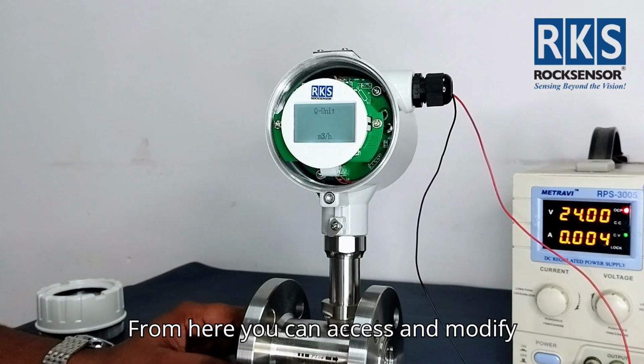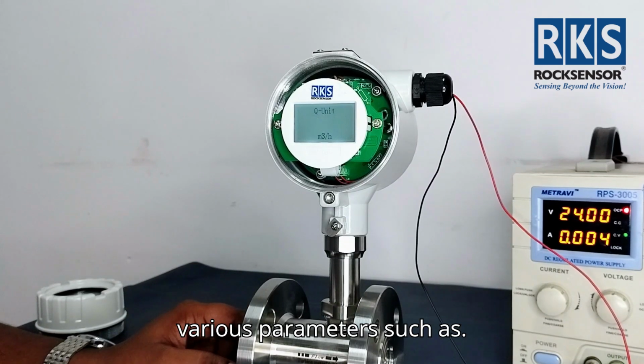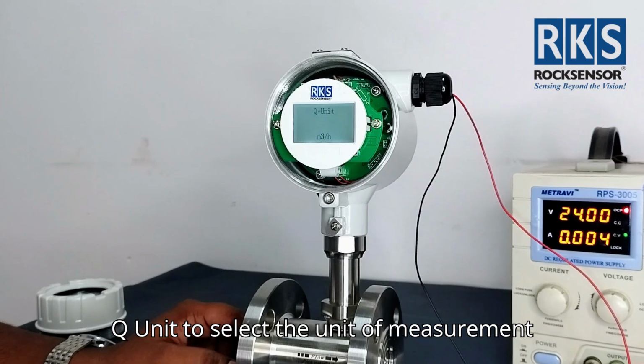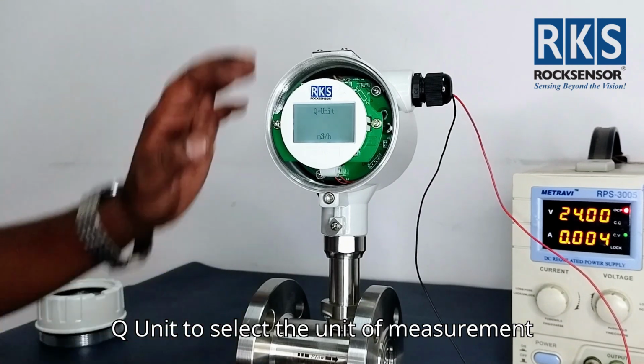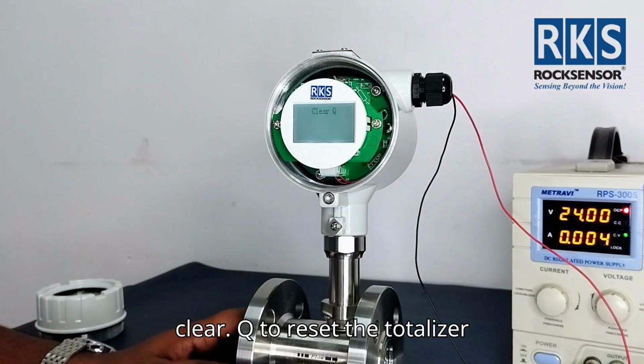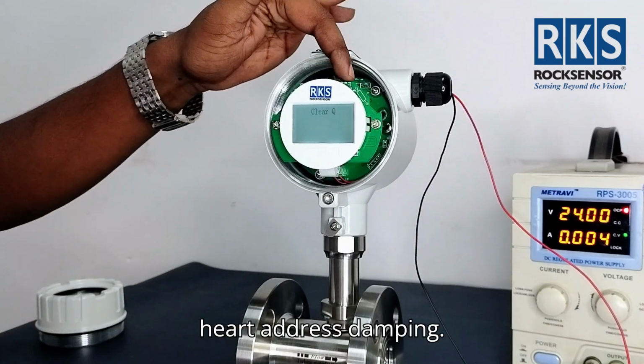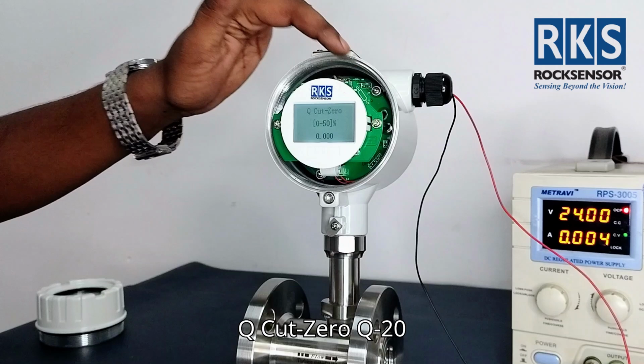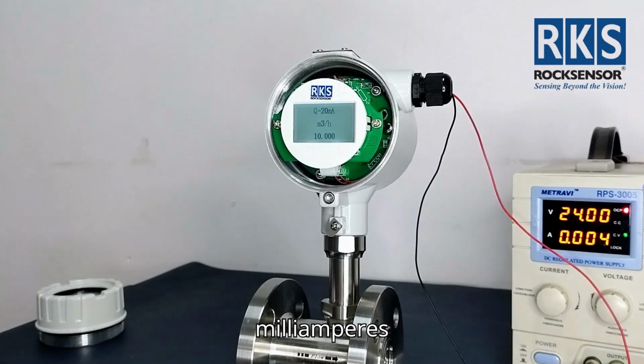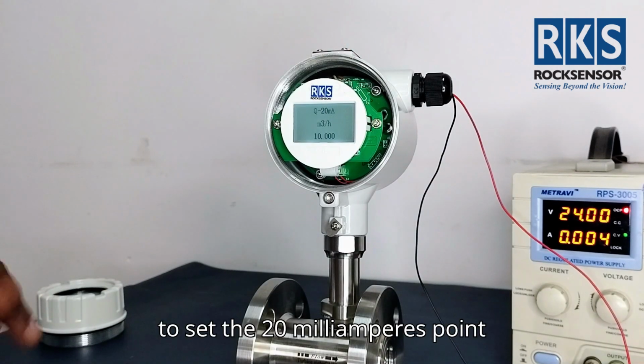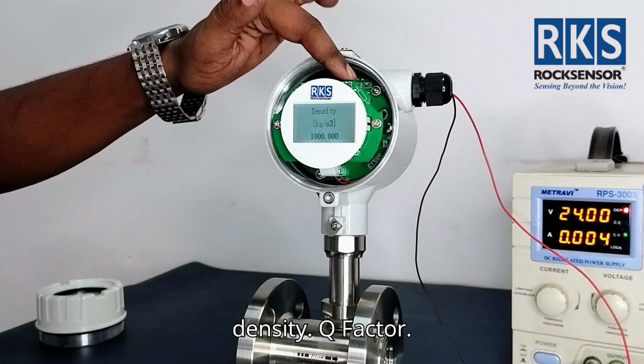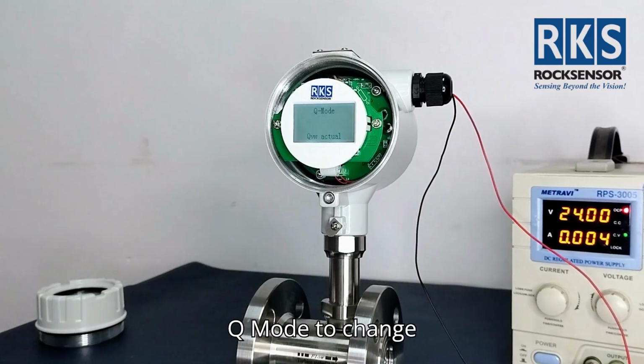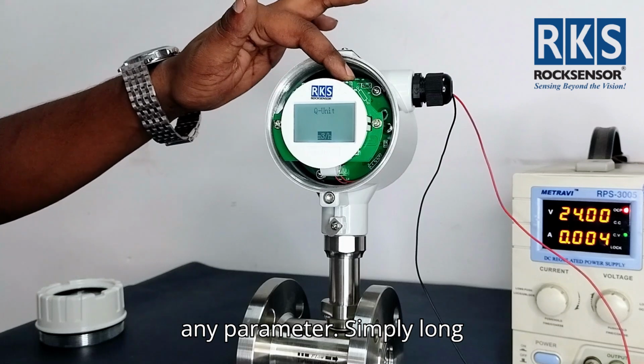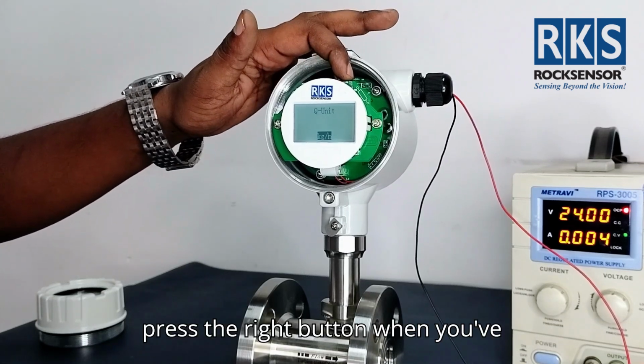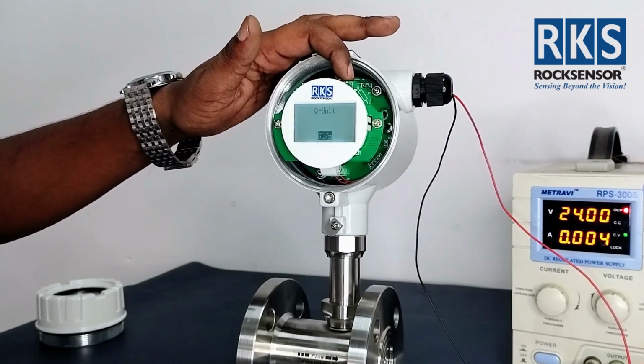From here, you can access and modify various parameters such as Q unit to select the unit of measurement, clear Q to reset the totalizer, HART address, damping, Q cut 0, Q 20 milliamperes to set the 20 milliamperes point, density, Q factor, Q mode. To change any parameter, simply long press the right button when you've selected the item you want.